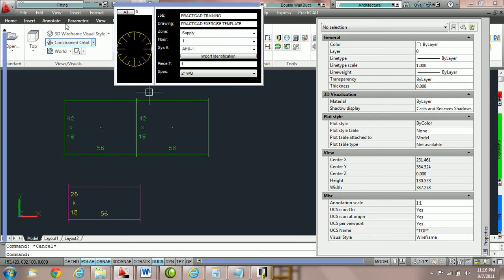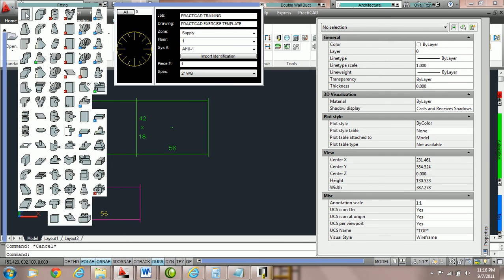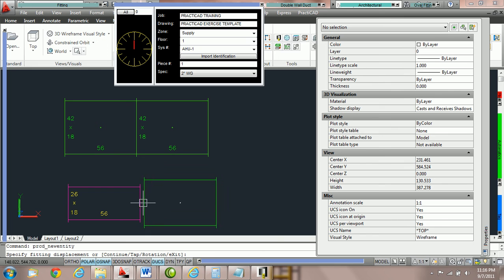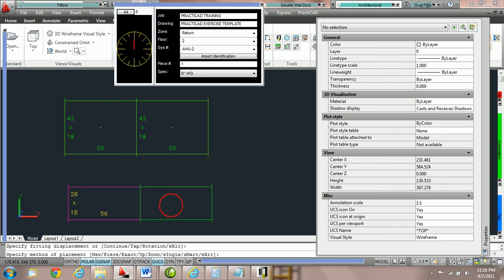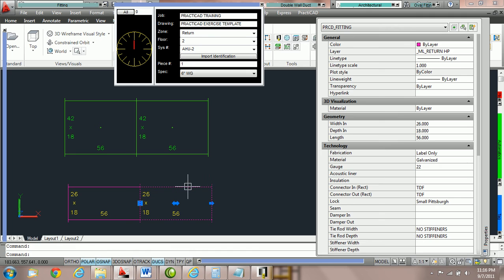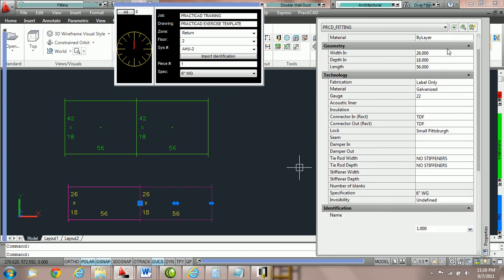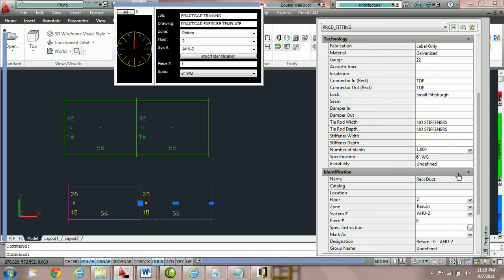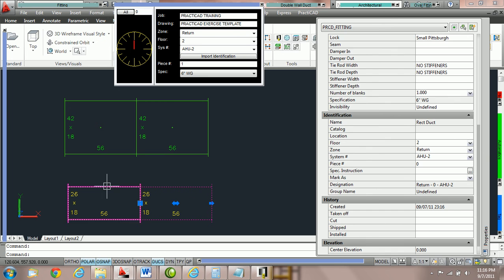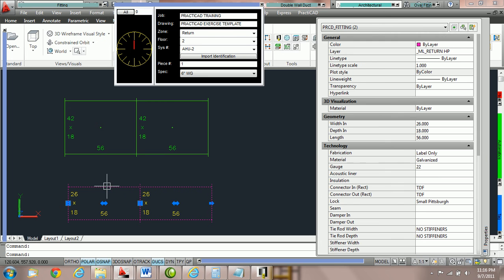However, if I go and grab another piece of duct and I decide to snap to this fitting and then we look at these properties, you can see by the layer changing color that it's obviously picked up the zone and spec. You can see that that duct has picked up floor 2, zone return, AHU-2. Completely different floor, zone, and system number properties and it's picked it up from the fitting we attached it to here.